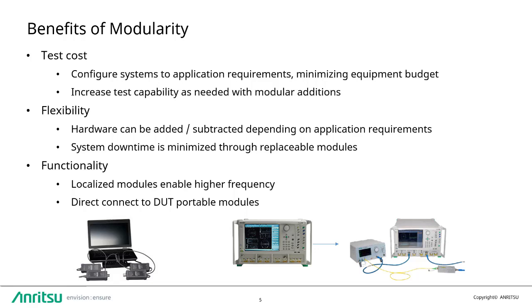Modular VNAs can also support other functionality like optical device testing with optical-to-electrical (O-to-E) and electrical-to-optical (E-to-O) extensions. Modular systems supporting small, independent measurement modules, such as one-port VNAs, enable direct connection to the DUT, improving dynamic range and measurement stability by eliminating interface cables.